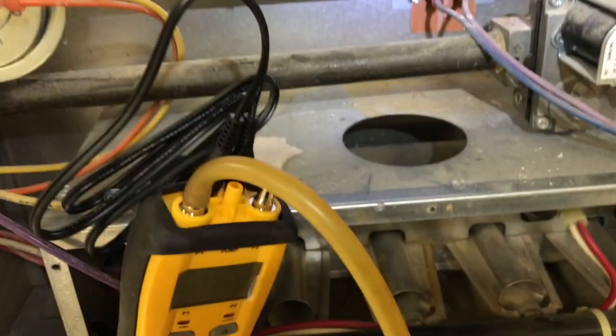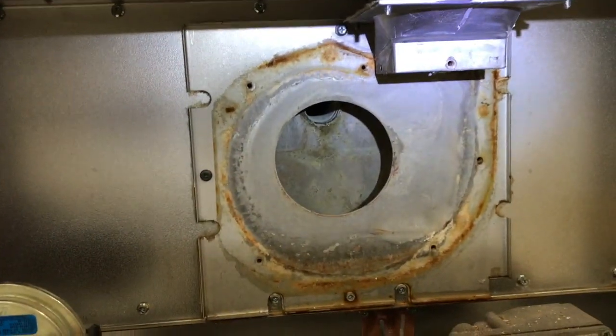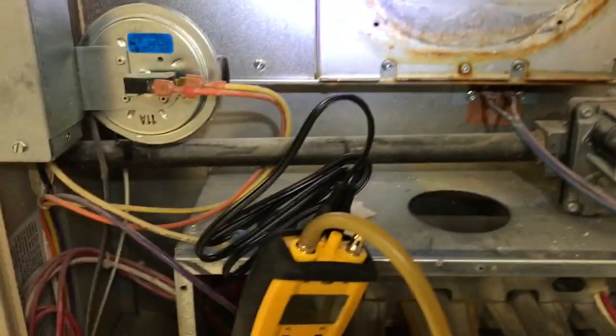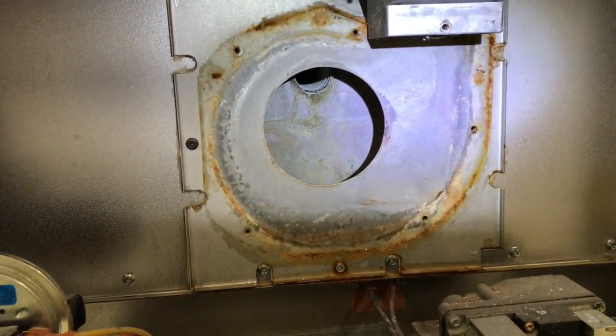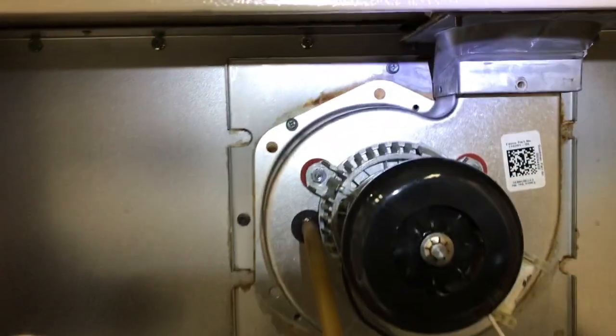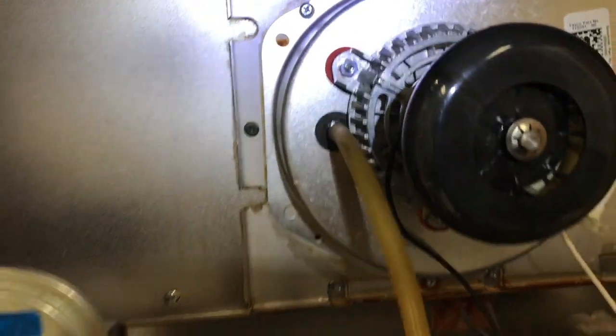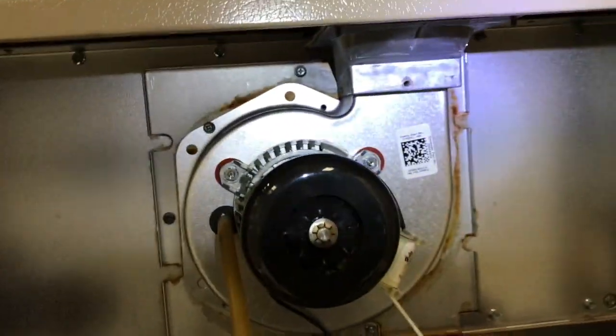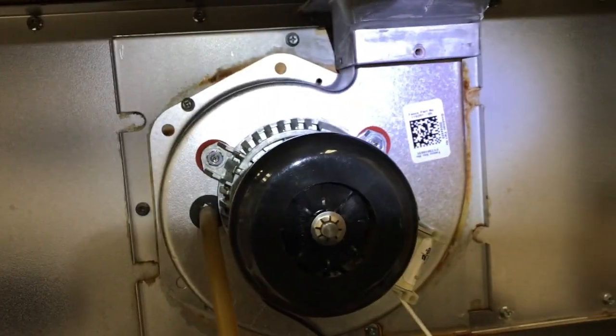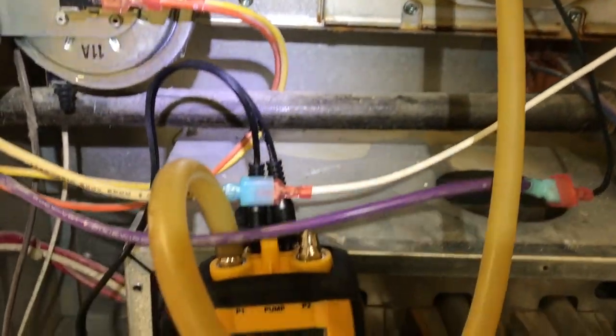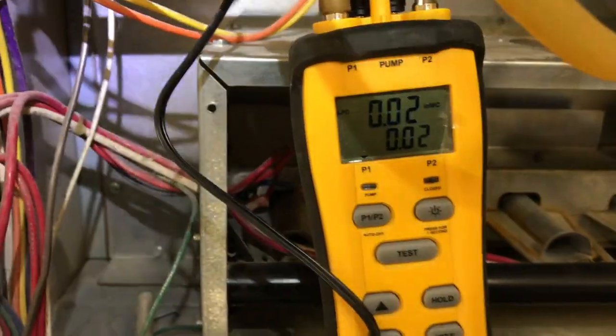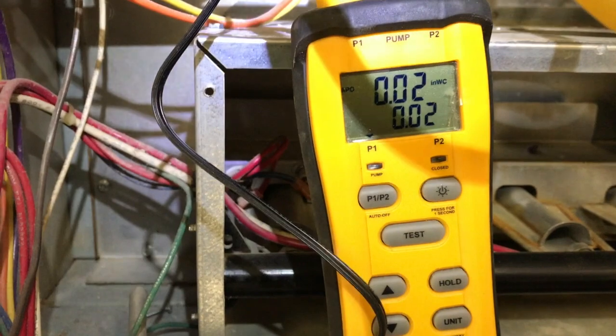So first thing I did was check the heat exchanger. It looked okay. Now I'm going to look at replacing this inducer motor, and I already got the part, so we'll throw it in and then we'll check the new inducer. Alright, I've got the new inducer in. I just put a couple of screws in to hold it in place real quick. The old motor is only pulling 0.50 or 0.45. Let's see what this one does when I flip it on here. Let's see if I can get that out of the way.